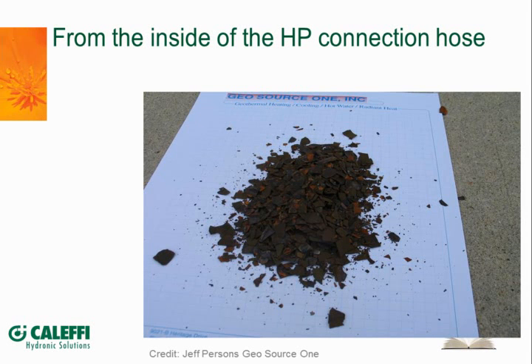So you had corrosion in the ferrous piping of the system. We can only surmise there's something with the molecular makeup of the rubber flex hoses, or perhaps some oxygen permeability in those hoses, but there's a mechanism there that caused this material to deposit inside them.